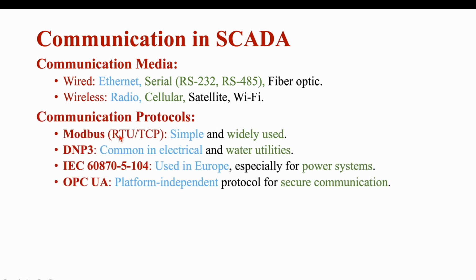What are the communication protocols used? Modbus RTU/TCP, which is simple and widely used. DNP3, common in electrical and water utilities. IEC 60870-5-104, used in Europe, especially for power systems. OPC UA, a platform-independent protocol for secure communication.